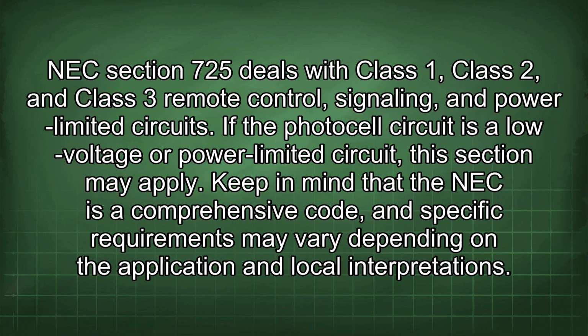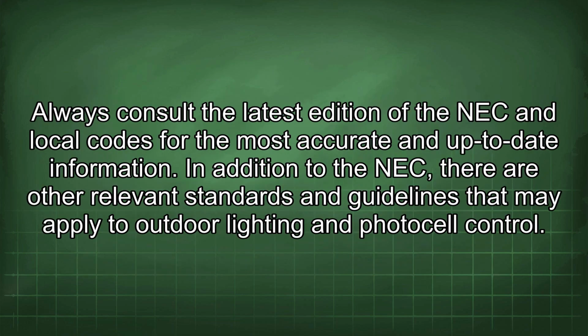NEC section 725 deals with Class 1, Class 2, and Class 3 remote control, signaling, and power-limited circuits. If the photocell circuit is a low-voltage or power-limited circuit, this section may apply. Keep in mind that the NEC is a comprehensive code, and specific requirements may vary depending on the application and local interpretations. Always consult the latest edition of the NEC and local codes for the most accurate and up-to-date information.